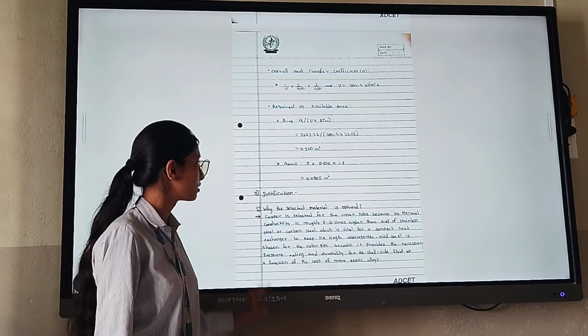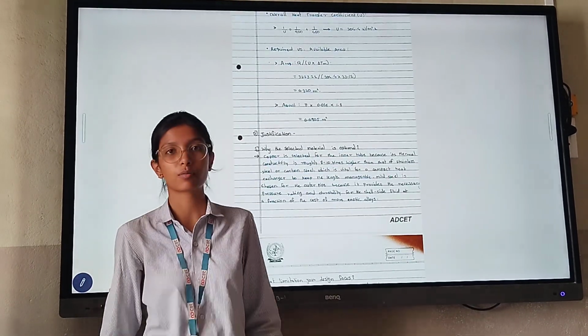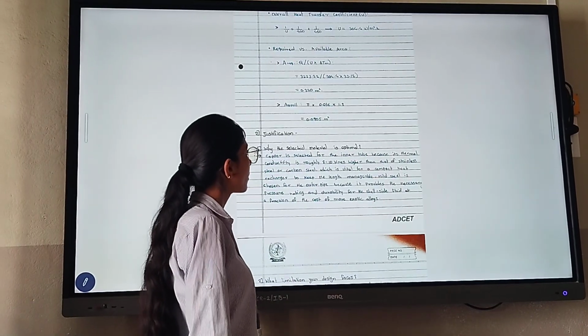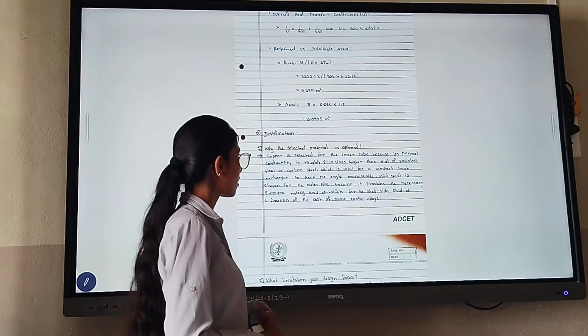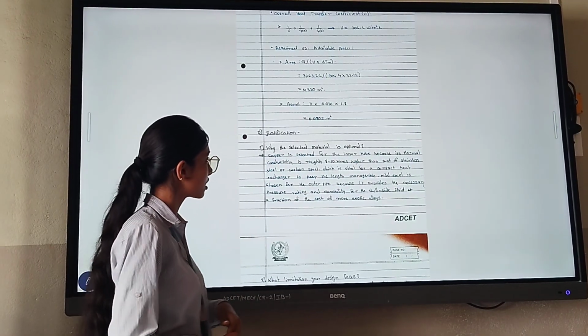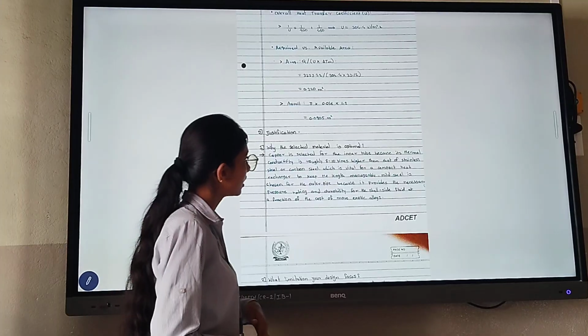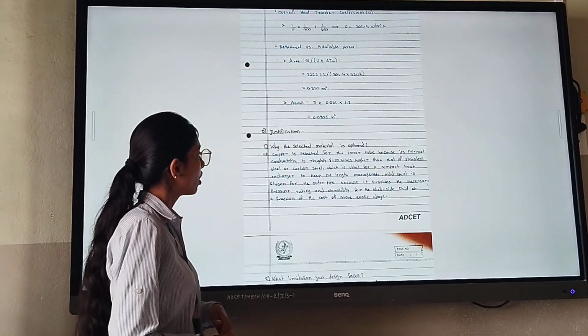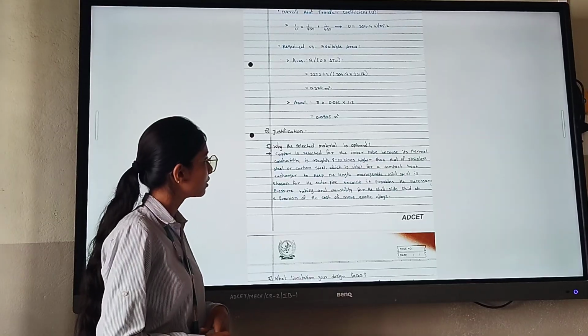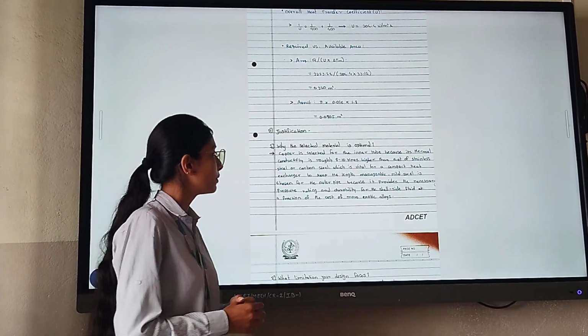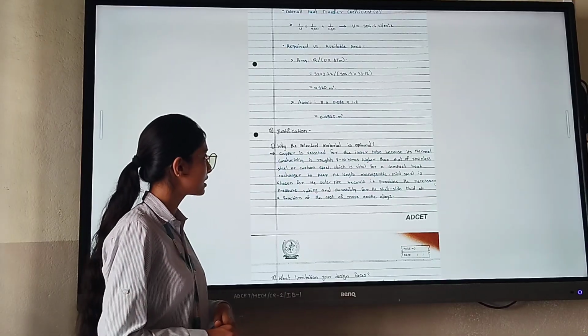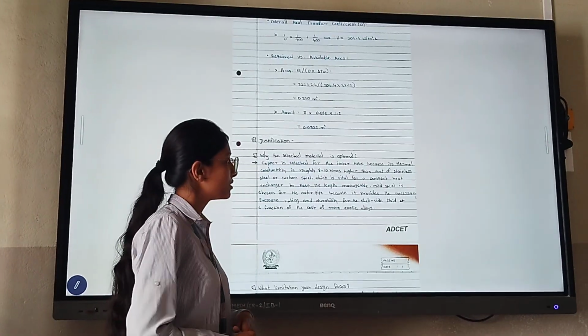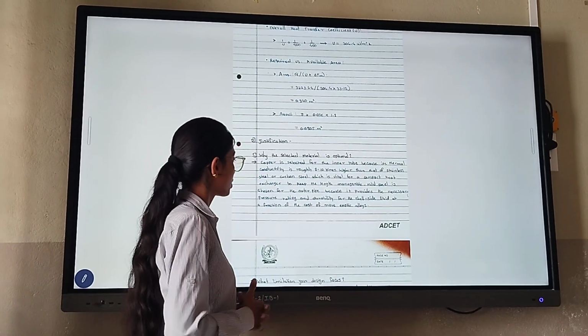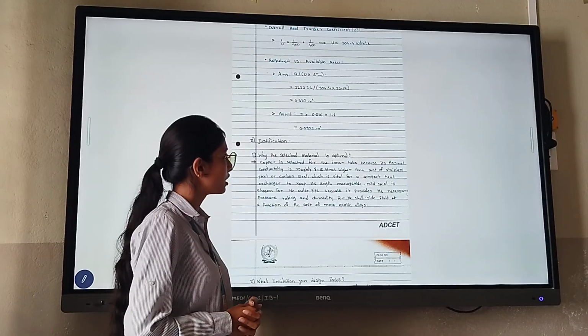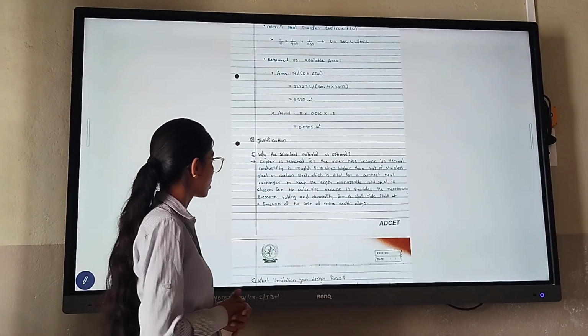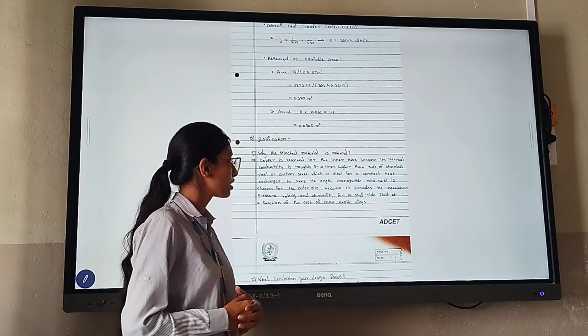Then justification. Why is the selected material optimal? Copper is selected for the inner tube because its thermal conductivity is roughly 8 to 10 times higher than that of stainless steel or carbon steel, which is vital for a compact heat exchanger. To keep the length short, machinable mild steel is chosen for the outer pipe because it provides the necessary pressure rating and durability for the shell side fluid at a fraction of the cost of more exotic alloys.